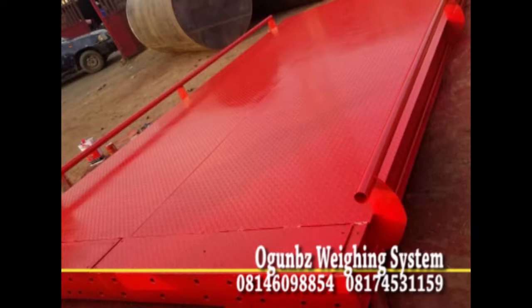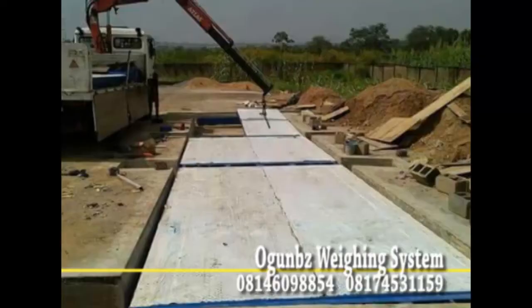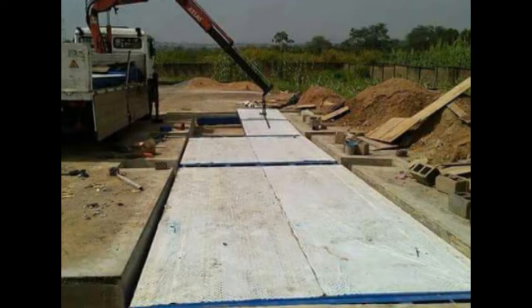So one of the things that you have to consider while trying to construct a weighbridge are some factors that could cause what you call immobilization in weighbridges. So let's consider some of those factors. The main causes that could lead to immobilization of a weighbridge are usually environmental factors such as water and lightning. It's so very key for you to understand this.